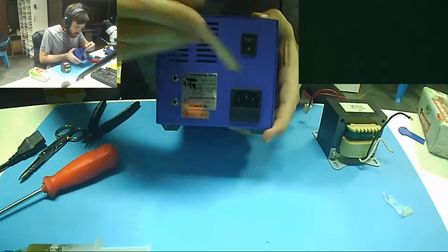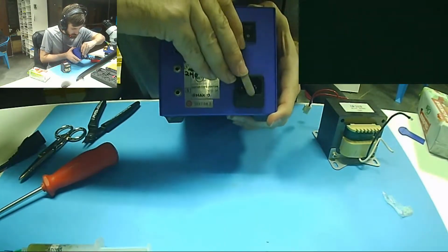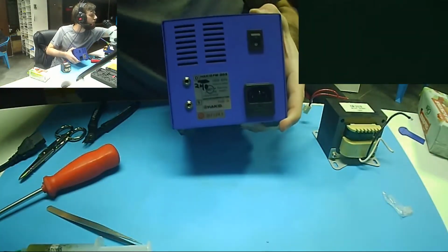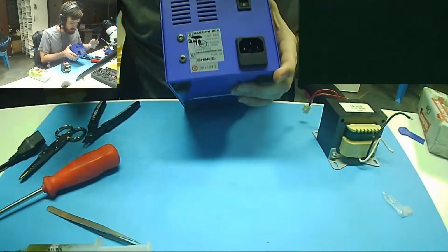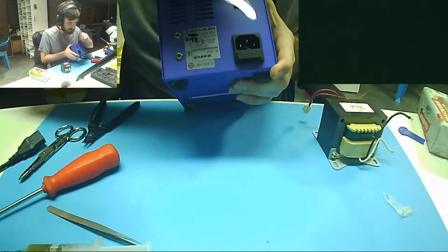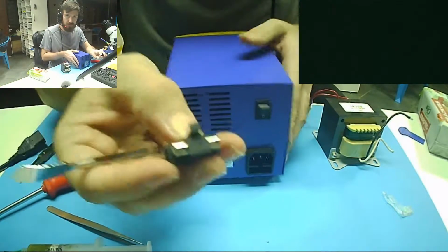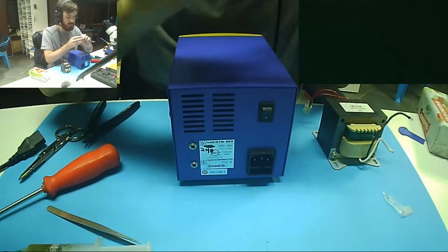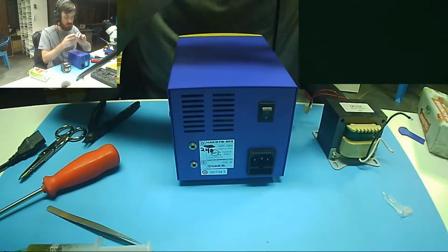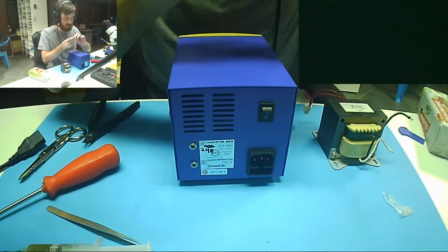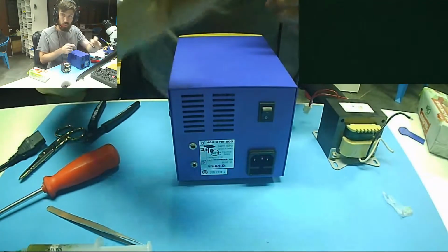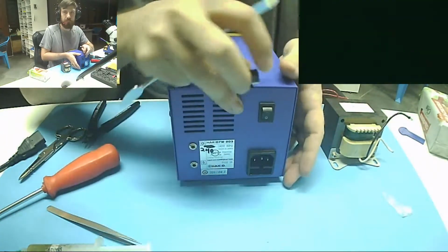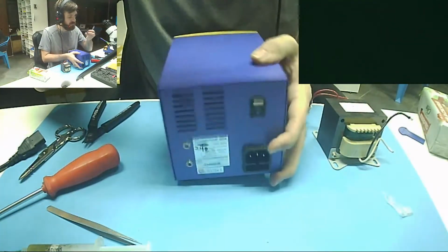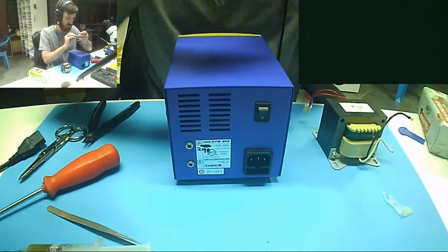I need to call up Hakko still and verify this, but this unit does have a fuse in it, and generally speaking there's a different fuse rating for 120 volt versus 240 volts. Right now it has a 3 amp fuse in it. Looks like a slow blow. Wire wound around it, whatnot. Let's see, does this actually have a... should say, I bet it says right here. No, 3 amp fuse, doesn't say.